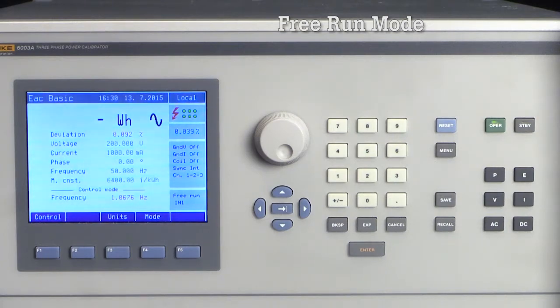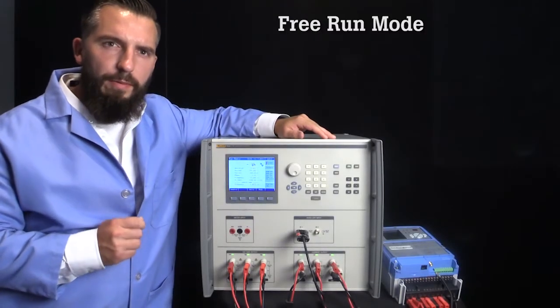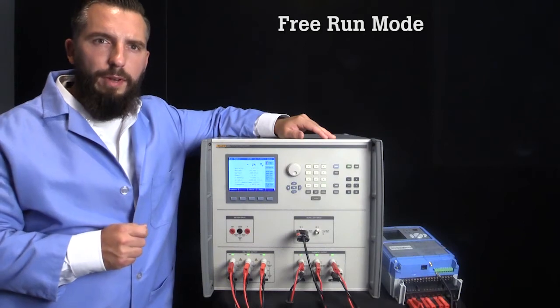The 6003A continuously shows the deviation between the measured frequency and expected frequency as a percentage. The meter we are testing is a three-phase class 0.2 energy meter and, based on this measurement, the meter is well within that specification window. This mode is useful for troubleshooting setups and is not recommended for the most accurate and repeatable energy calibrations.